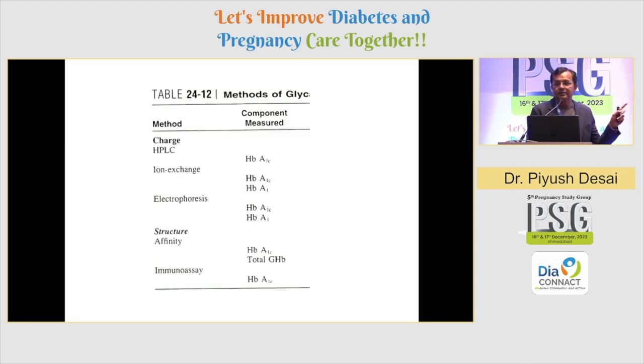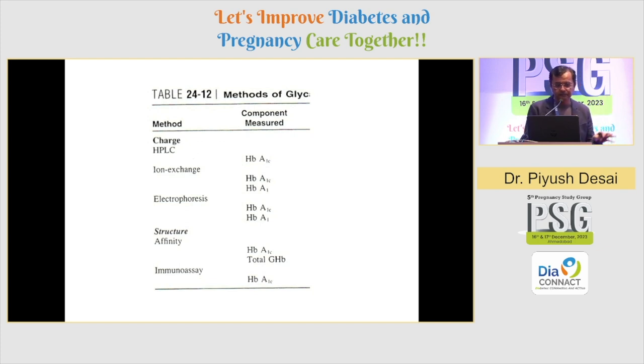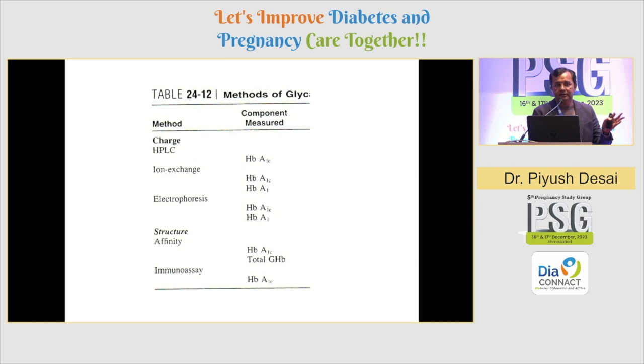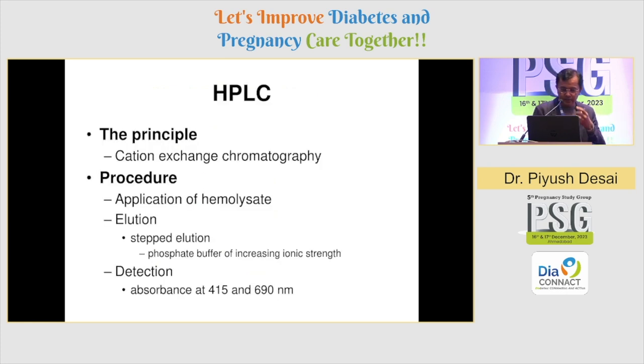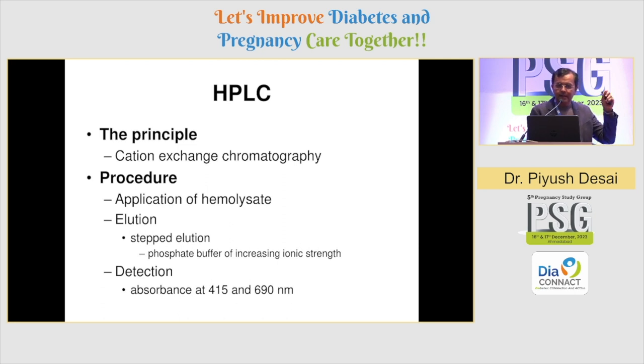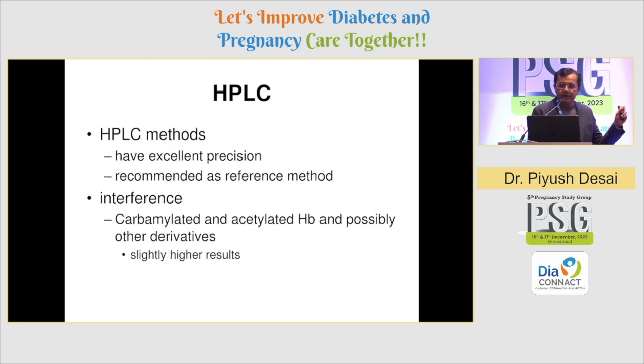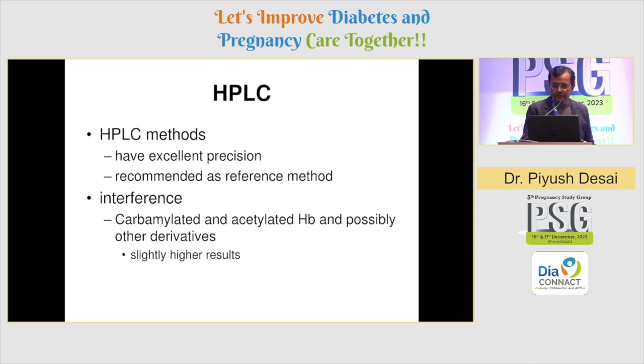The gold standard method for HbA1C is HPLC (ion-exchange chromatography). Electrophoresis methods exist but are not popular or well standardized. Boronate affinity method is used for point-of-care devices, which are widely used. Immunoassay is used by a number of labs, but standardization may vary depending on which type of immunoassay is used. HPLC involves three steps: application of hemoglobin, elution, and detection. It offers excellent precision, which is why it is the gold standard.